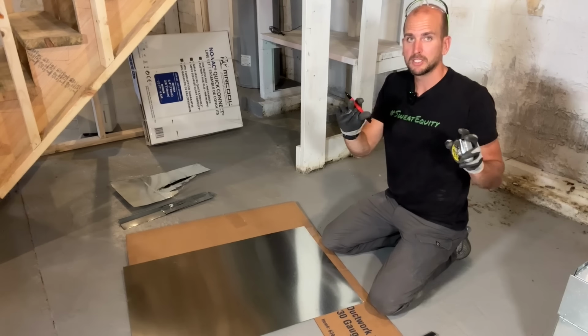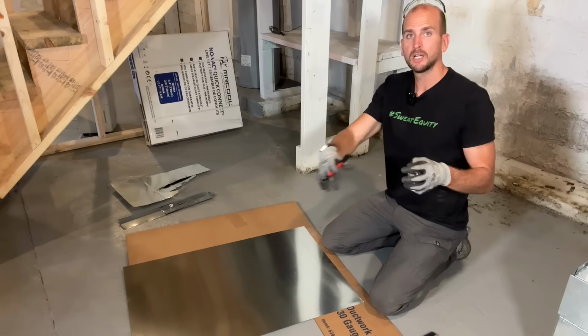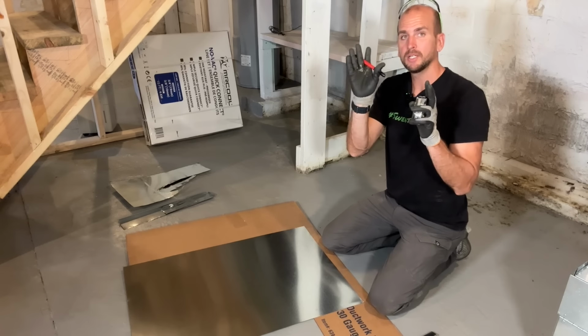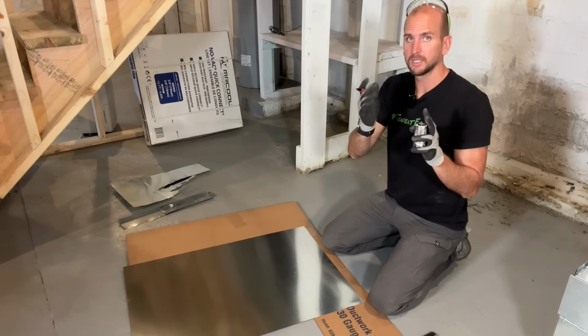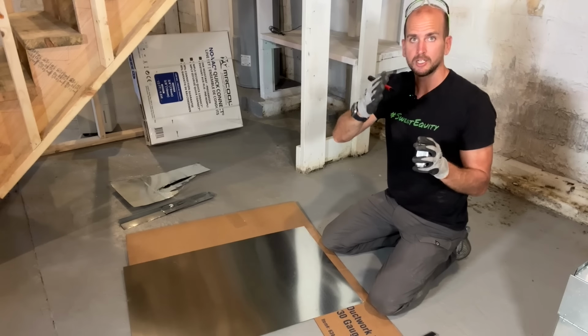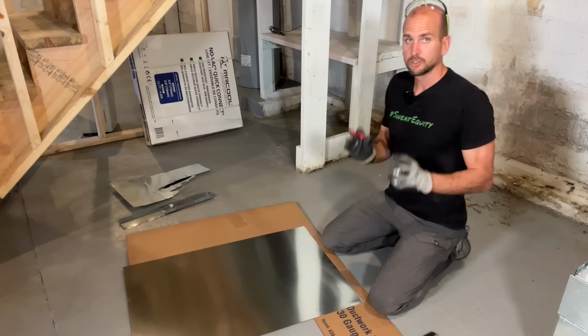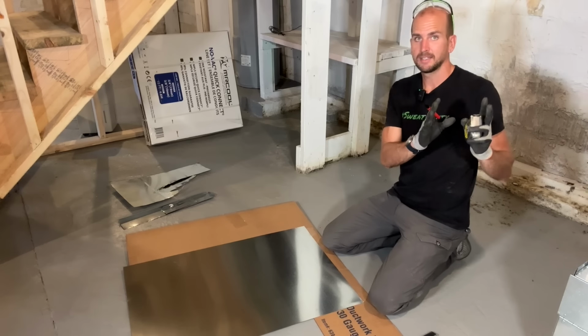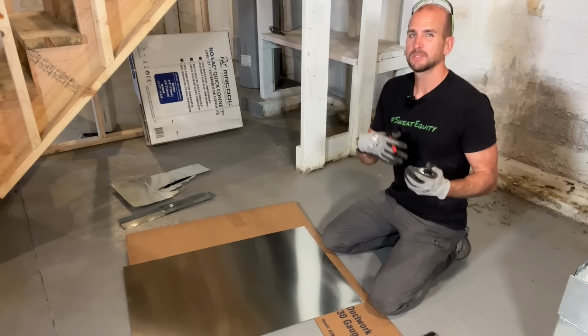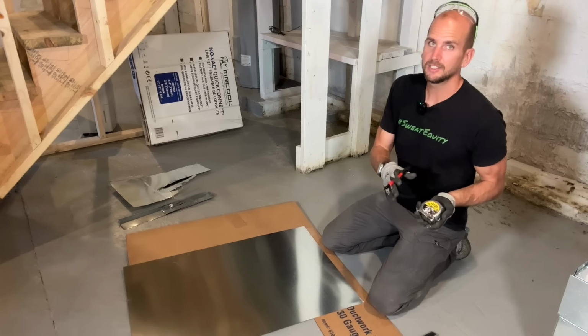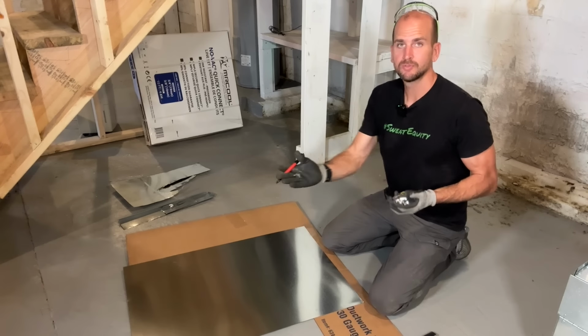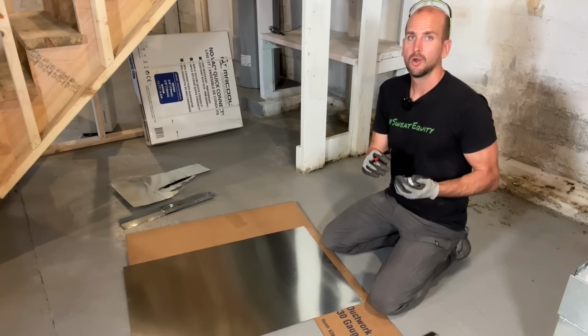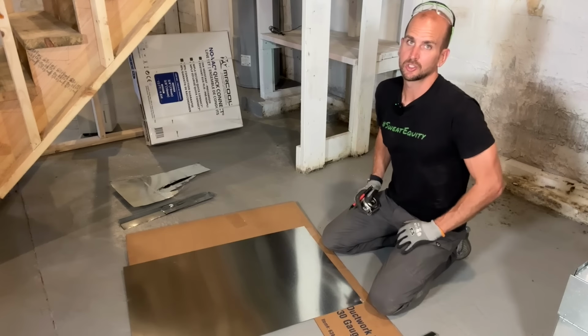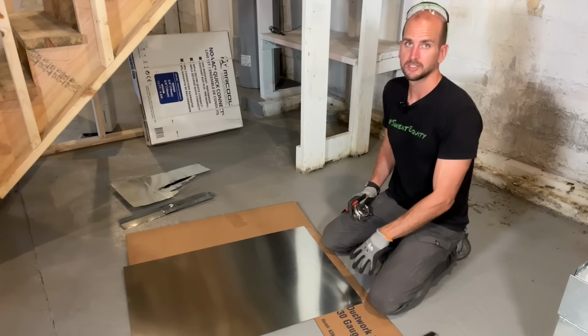So you take your measurements, your biggest measurement, you cut off your rough shape so you can put it up to where you need to do your custom cut, and then you do your markings, hit your straight edge, and then you'll start to get your actual piece sized to exactly that size. Take your time, especially when you get started, because you can easily forget to add the 1 inch for that 90-degree bend, or measure slightly off, and then you're starting over, having to go get additional pieces of sheet metal.